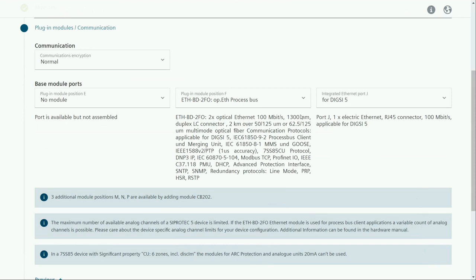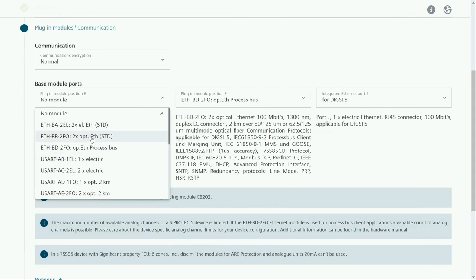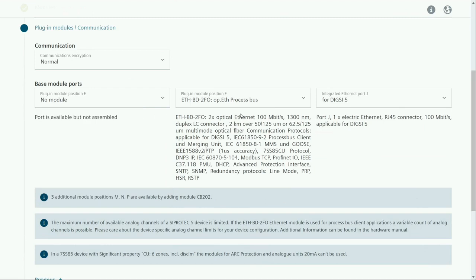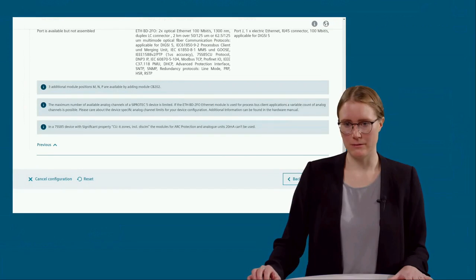If you really want a device with these up to 48 measuring points, the slots in the base module would not be enough, because then you need 3 Ethernet BD modules and only 2 slots are available. In this case, you need to add an additional expansion module CB202. And then you have 3 more slots available to add Ethernet BD modules. In our case, this one would be sufficient. And of course, if you want substation communication, you can add another Ethernet BB module, for example, as well. But I go with no module, only our Ethernet BD module.